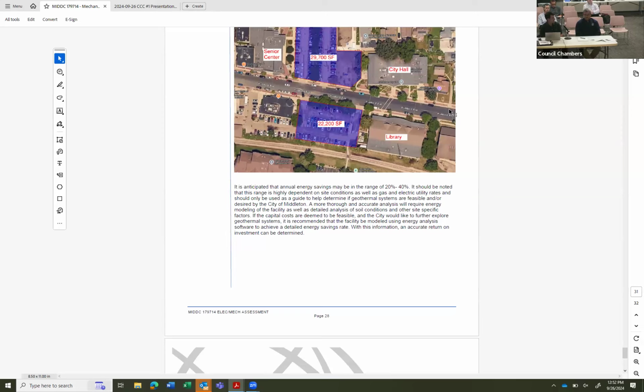Yeah, it would increase. I don't know if we have a specific number on the level of increase, but we can certainly look into it, because that is the biggest part of the level 2 upgrade. With using that VRF system, there's going to be a larger service required than for the geothermal system. The geothermal will potentially require an upgrade, but the level 2 variable refrigerant flow system would certainly need an upgrade, because it would generally require probably twice the electrical capacity of the geothermal system. And then, is the geothermal system a closed system, or do you discharge water?